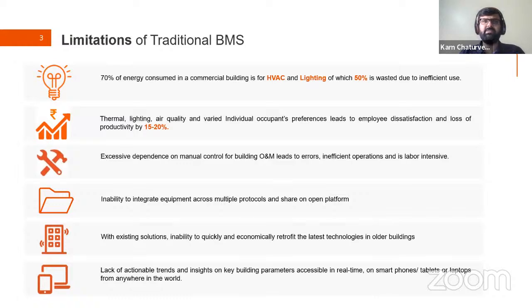At the same time, I think this is one of the largest issues: we as consulting engineers specify a lot of points, alarms, and trends, all captured in the BMS system. But over time, the knowledge of these trend points and alert points goes away. When the client comes back and asks where all these features are, you have to point them back to it. And if they want to get that data out, they have to do it manually using Excel sheets, thumb drives, or internet file transfer, which is not very immediate.